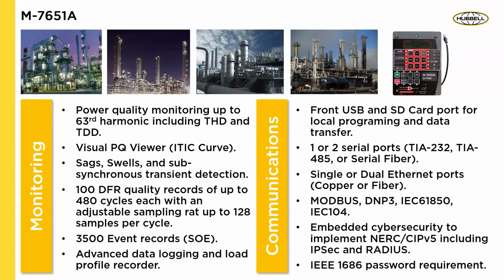On the monitoring side of things, it's very powerful. On the power quality side, it can do up to the 63rd harmonic, including THD and TDD. Again, visualization is key here, so we have a power quality viewer, and you can see all the events there. You can have oscillography, data logging, sequence of events, and all kinds of recording capability that a modern digital relay would have. It also has a front USB and an SD card port, and I'll talk more about that later. On the communications side, we have single and dual Ethernet ports and all the protocols that a normal industrial plant would be using, like Modbus, DNP, 61850, and IEC 104.